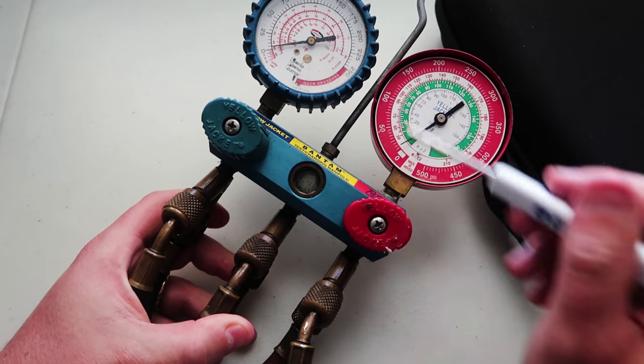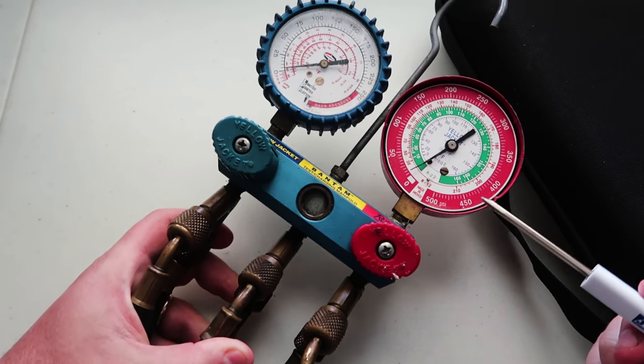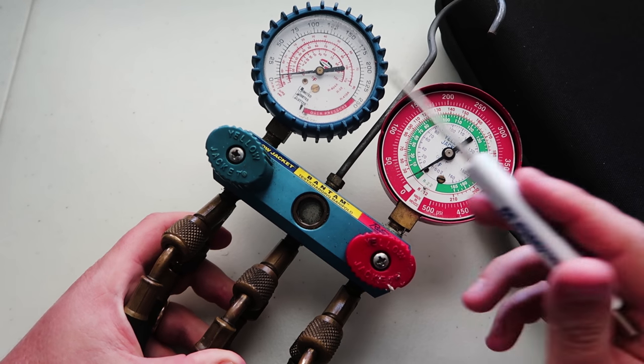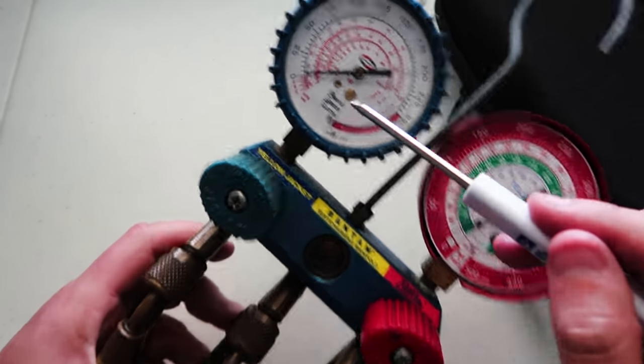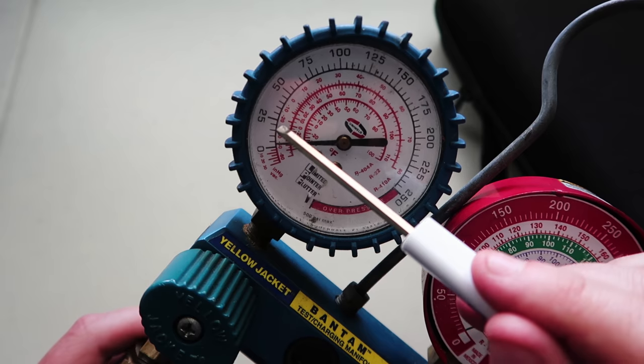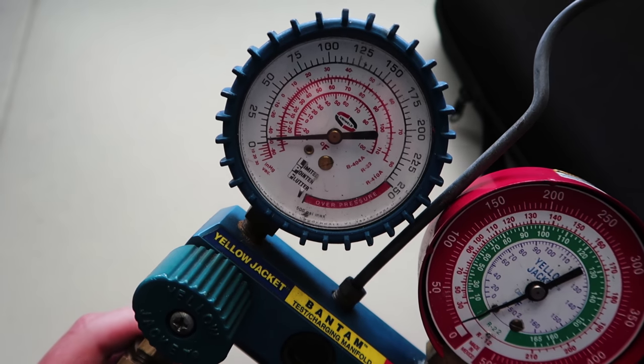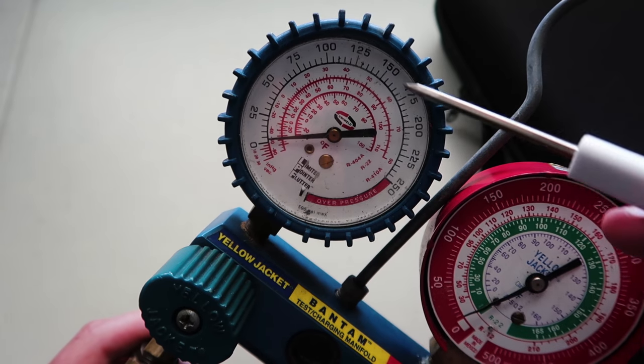The first thing to note is that these are what measure the pressure, and then we can convert that pressure into temperatures in order to calculate things like superheat and subcooling. These scales on here on the inside show different temperatures for different refrigerants, and when the needle points at those temperatures, that's what we call the saturation temperature. That goes along with the pressure that's listed on the outside.